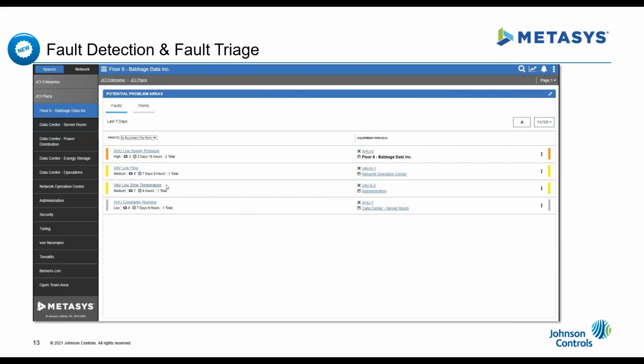Being able to detect those kinds of things, an air handler pushing out too much cold air, is extremely important to know, but it doesn't have to be an alarm per se, but it should be a fault that you look at as a common part of the day. The thing that we don't want to do is have a human running around looking for all these faults, right? Nobody has the time to do that. So we want the BAS system to do that, and that is really what fault detection allows us to do. So if we can move on to the next slide there.